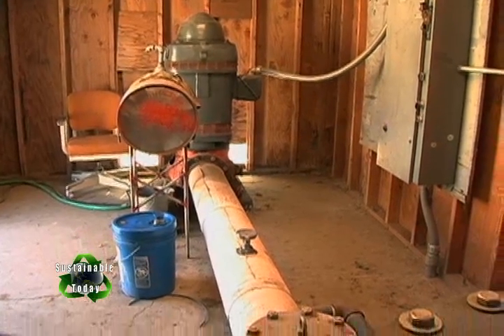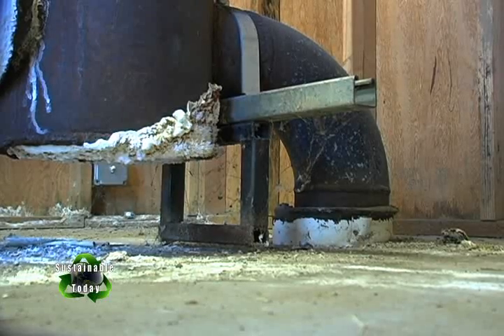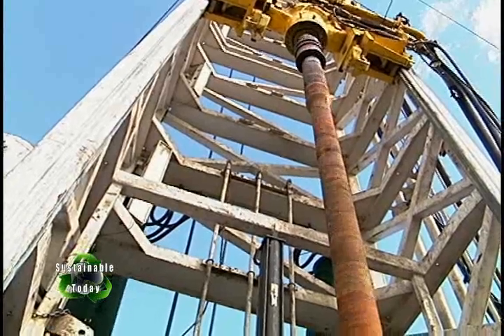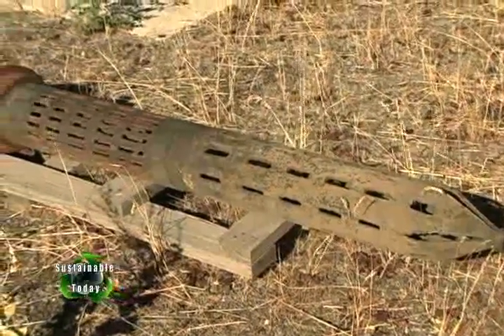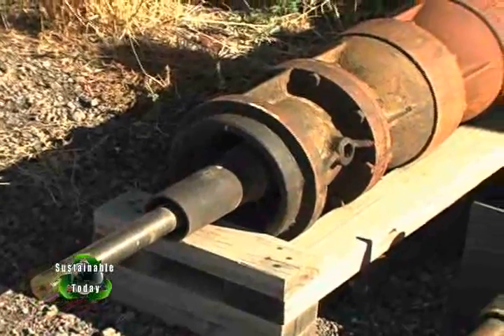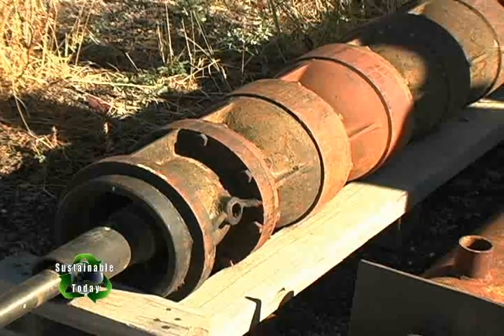We're running three wells. We have a variety of wells that produce different volumes. Our small well — well number two, which is behind us — is drilled to a depth of about 1,200 feet. Well number five, our big well, produces about 450 gallons a minute and is drilled to about 1,600 feet. Well number six is drilled to about 1,800 feet deep. Our largest drilled well, drilled in February of 2009, is over a mile deep and produces a little over 2,500 gallons a minute of 194 degree water. These are the actual pumps at the bottom of the well column. The perforations are where the water is inlet, and above that is the bowl assembly. The shaft is turned by the motor, driving the impellers in the bowl assembly, which elevates the water and brings it from the aquifer up to the surface.